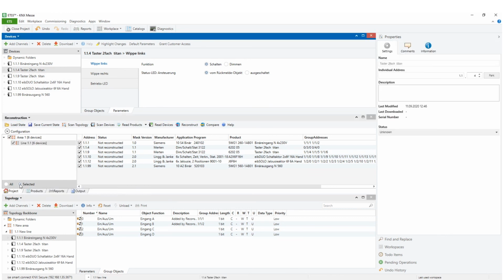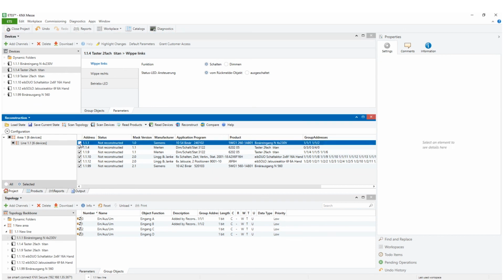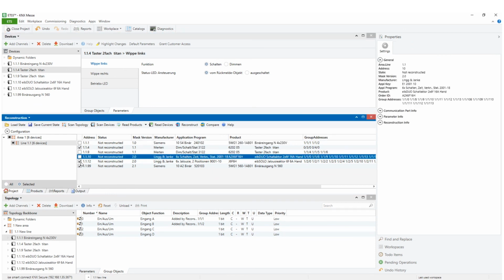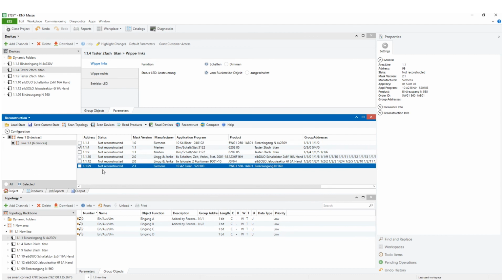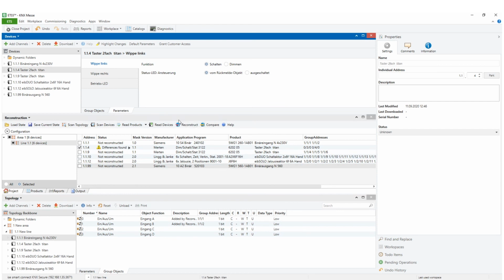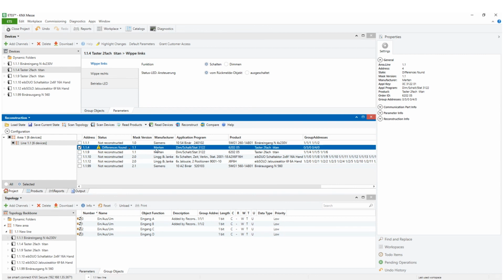For this I change to selected, and undo all the boxes. And I start compare. You see that the Reconstruction app found the difference in device 114. The device is marked with a yellow exclamation mark. By clicking at this device, you will get more information about the change at the right side. The Reconstruction app has many more functions, but their explanation would go beyond the scope of this seminar.